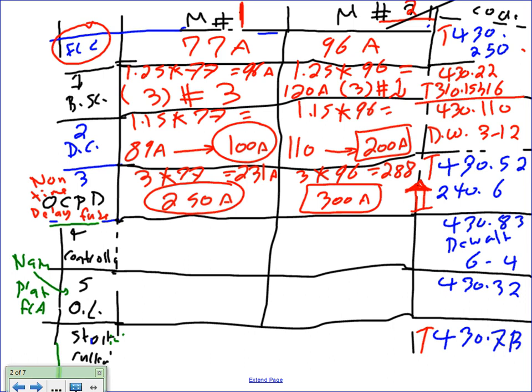Now, some of you might ask, Chad, how am I going to fit a 250 fuse in a 100 amp disconnect? If this fuse is inside this disconnect, which it could be or not, then what are you going to do with this disconnect? Up it to handle this. What's the next standard size to handle this one? 300.